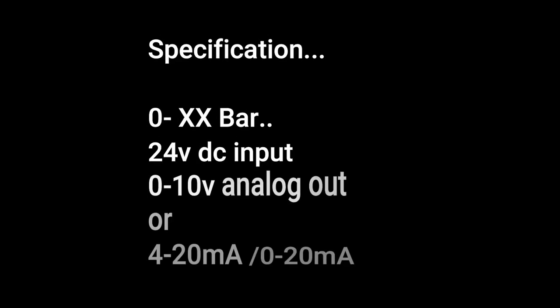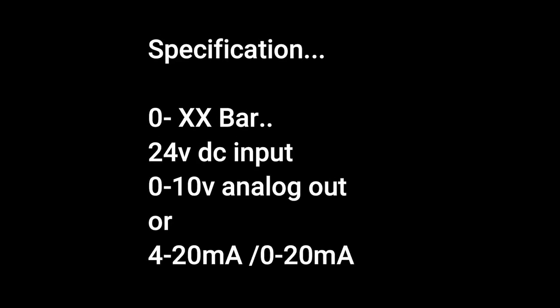The pressure transducer works with always 24 volt DC. Whatever the rated bar is, the same is converted to the analog output. If it is 0 to 10 bar, then 0 bar equals 0 volt and 10 bar equals 10 volt, and same for 4 to 20 milliampere as well as 0 to 20 milliampere. If it is 0 to 16 bar, then 0 bar equals 0 volt and 16 bar equals 10 volt or 20 milliampere.